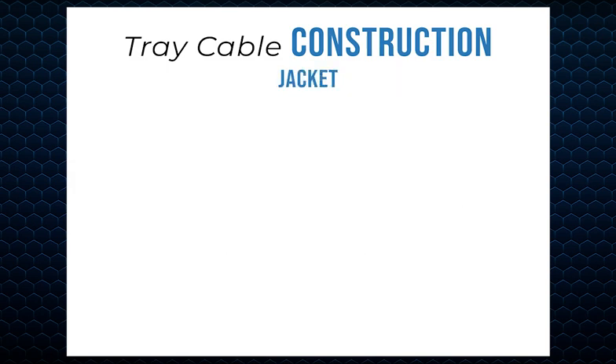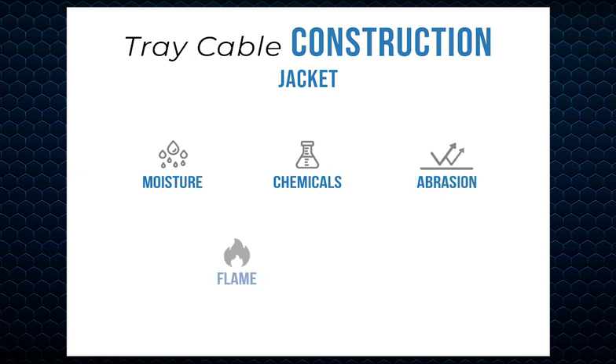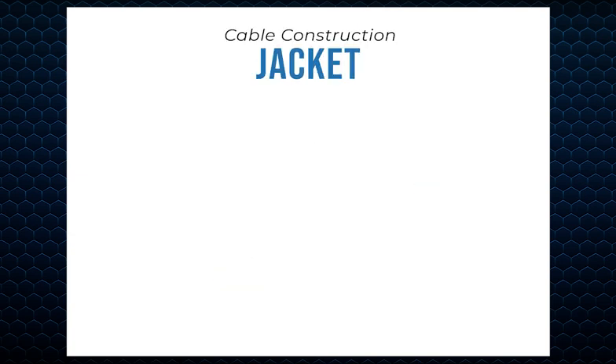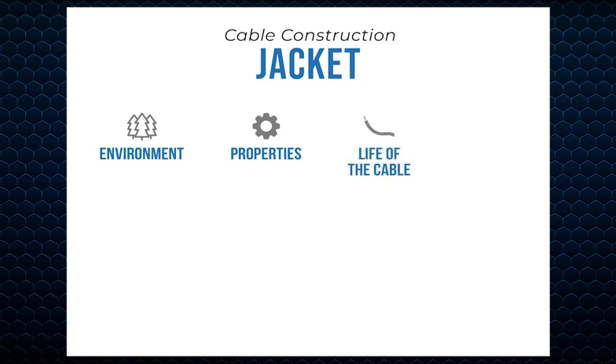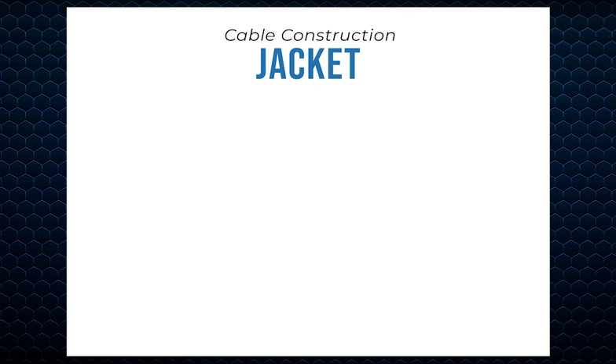All tray cable designs utilize an overall outer jacket as protective covering. These jackets provide the cable core protection from moisture, chemicals, abrasion, flame, and can be rated for direct burial. Selection of the outer jacket compound is dependent on the environment in which the cable is installed, the properties of the compound, the life of the cable, and the ratings required.